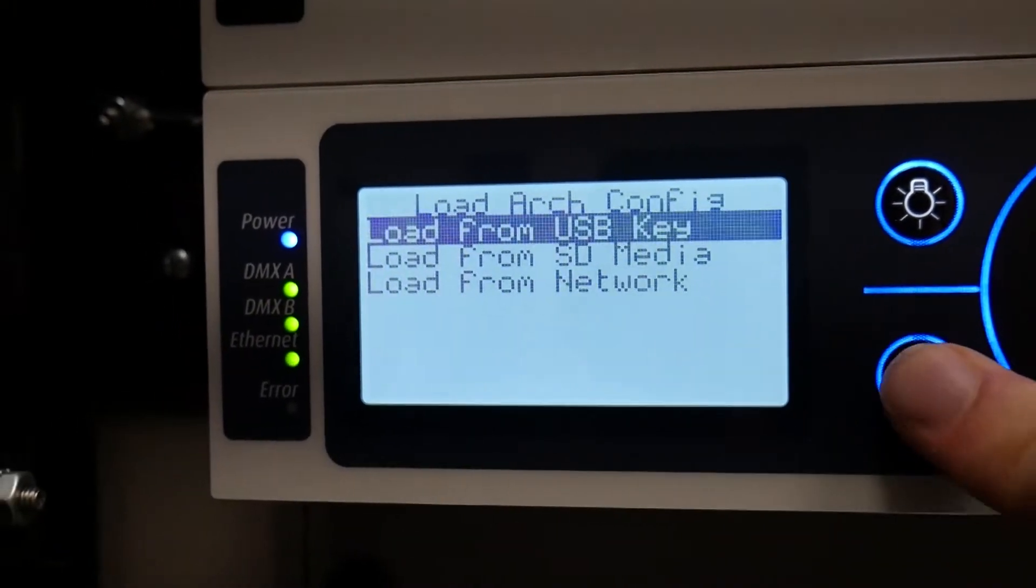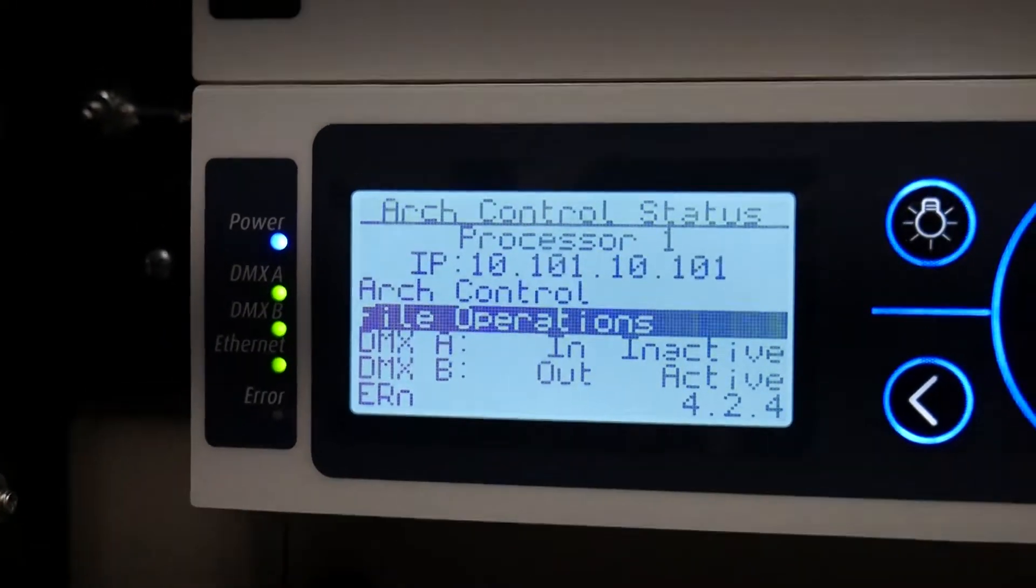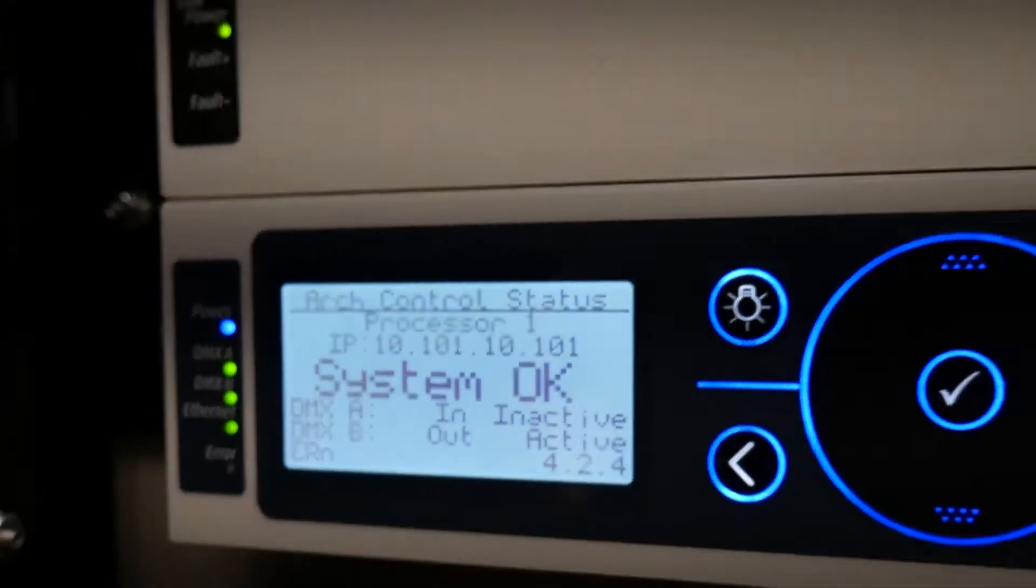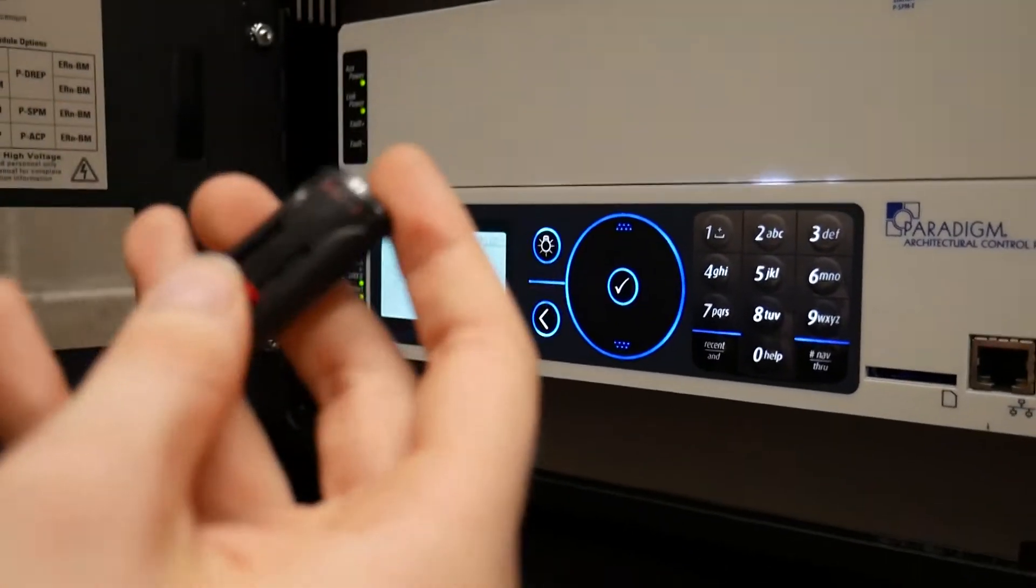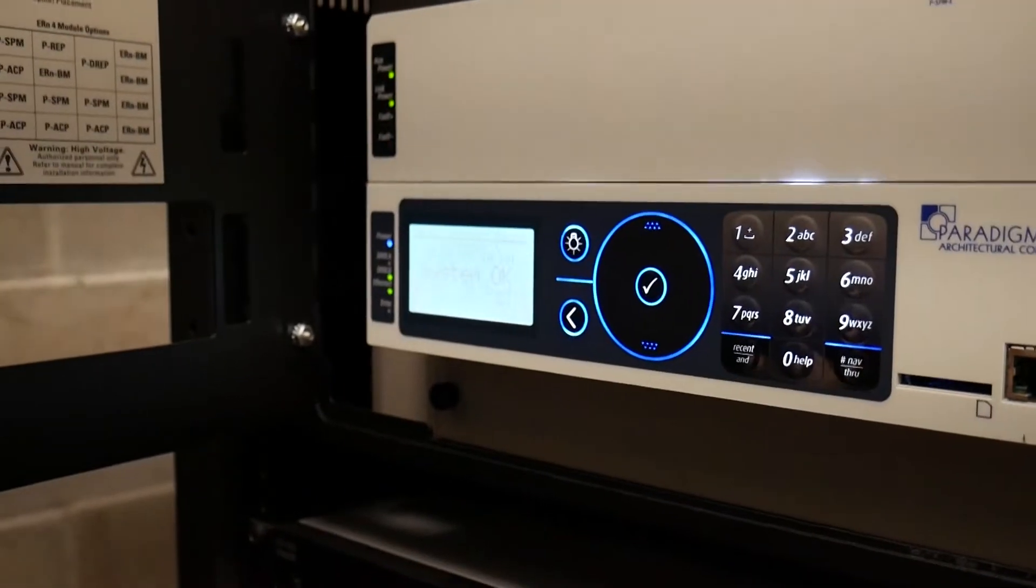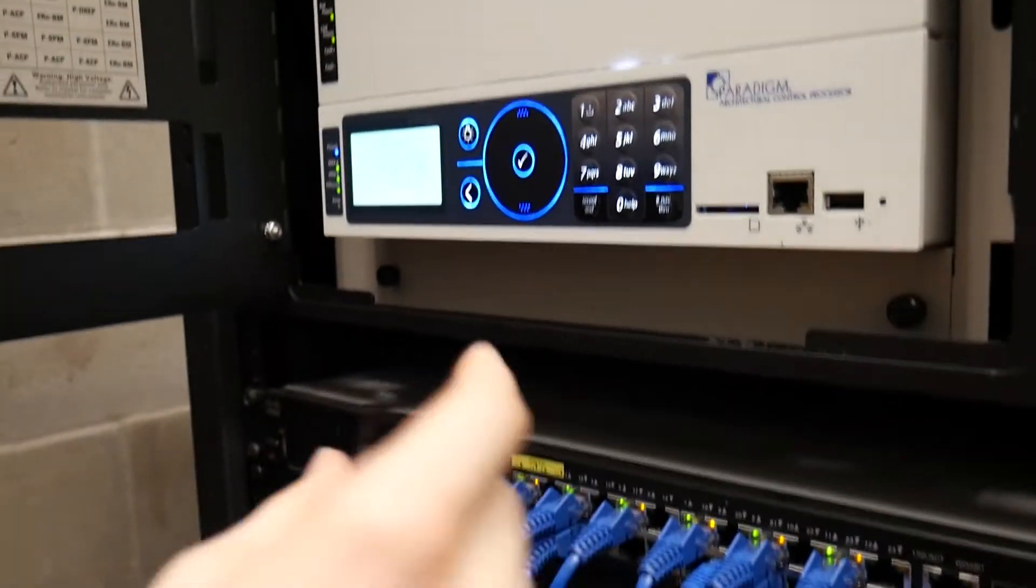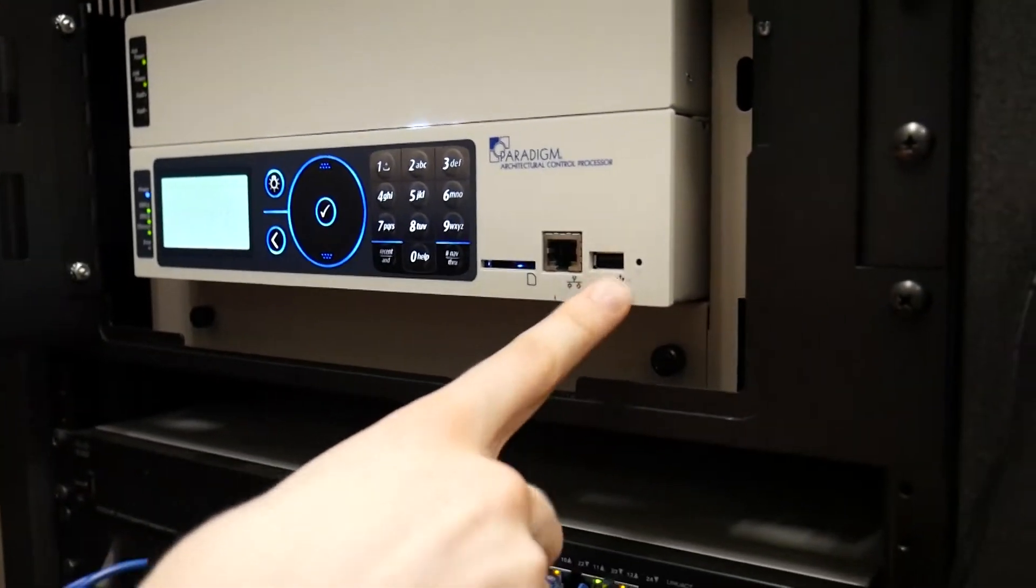But basically what happens is with our PACP specifically, sometimes the USB won't be recognized. Now if the USB is not recognized, what ETC tells you to do is to take your tool right here and restart the system. To restart the system there's a little reset key right there.